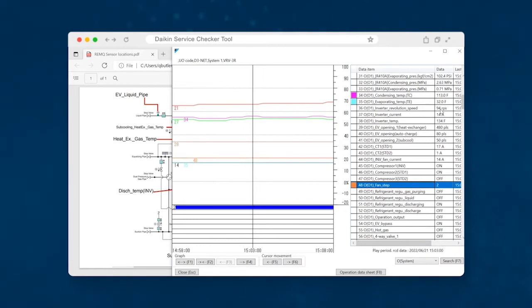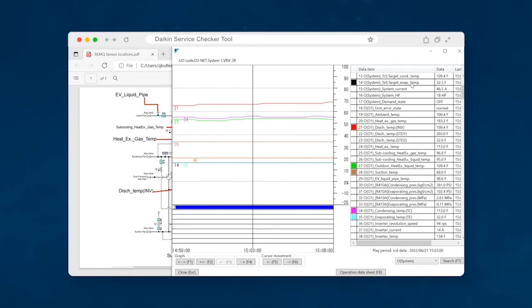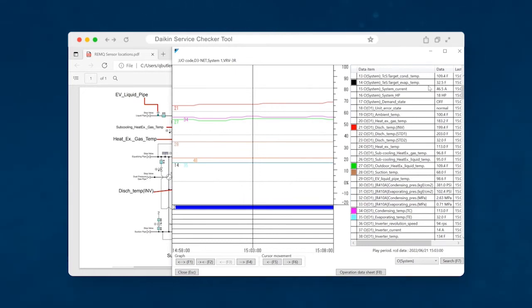And so with this compressor ramped up to 94 revolutions per second, this compressor probably turns at full speed, it might turn 150 revolutions per second. So it's at the upper end of the speed. And you notice that the fans are turning really slowly. So this is at the bottom of the range for fan speed. So this is in order to help keep our saturated evaporator temp in accordance with our target evap temp. So you notice that these two are almost spot on, right?